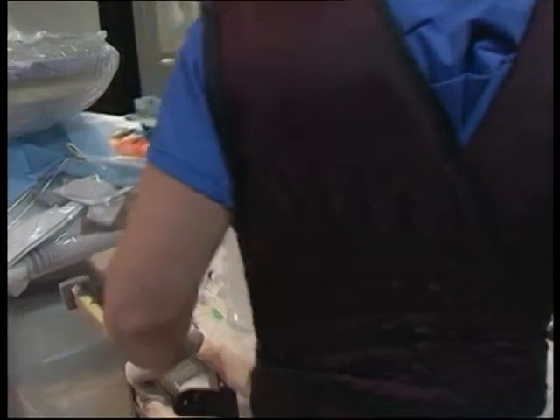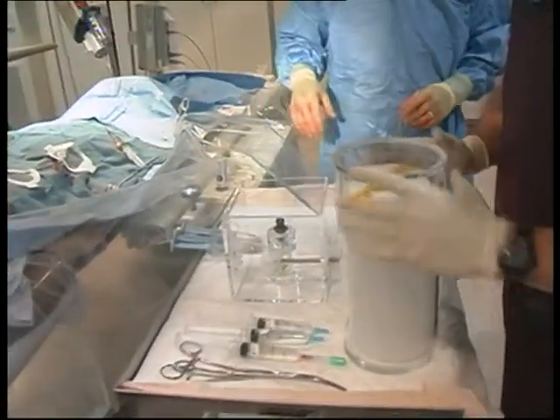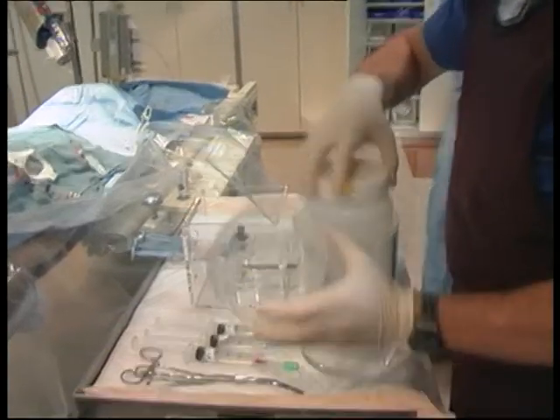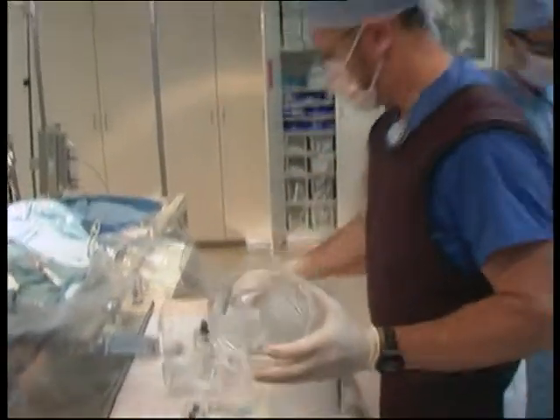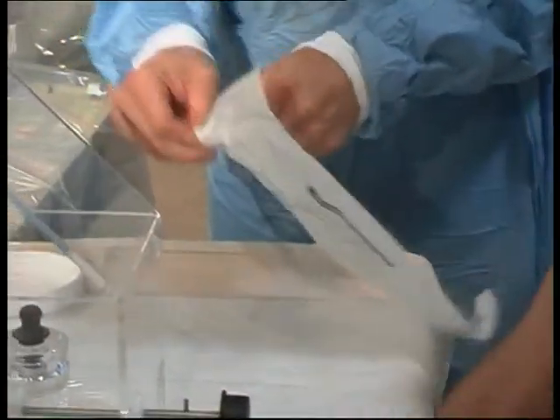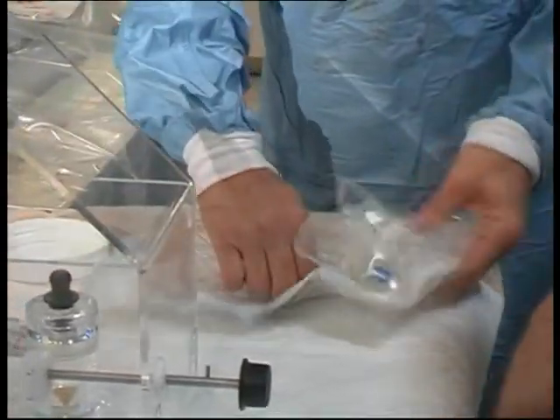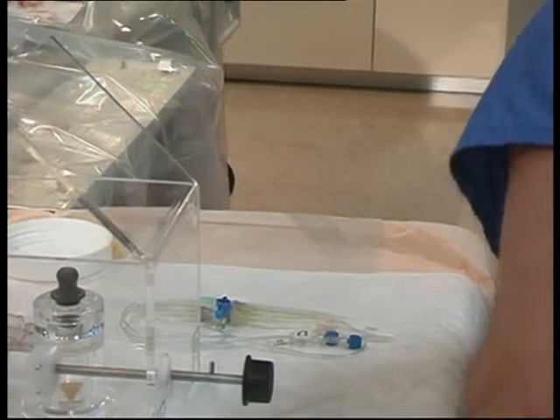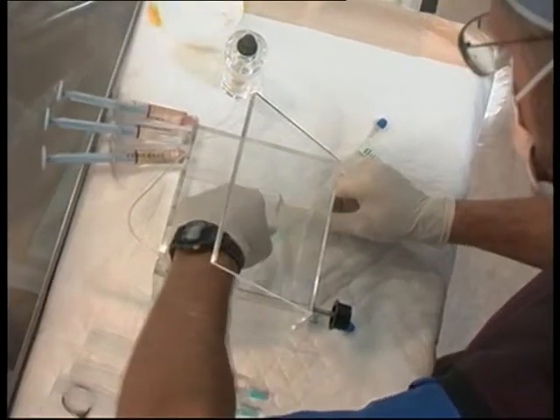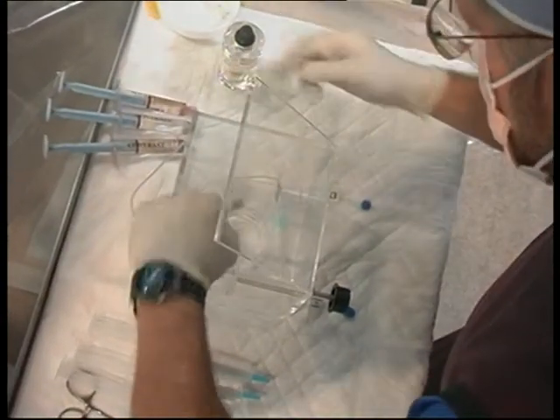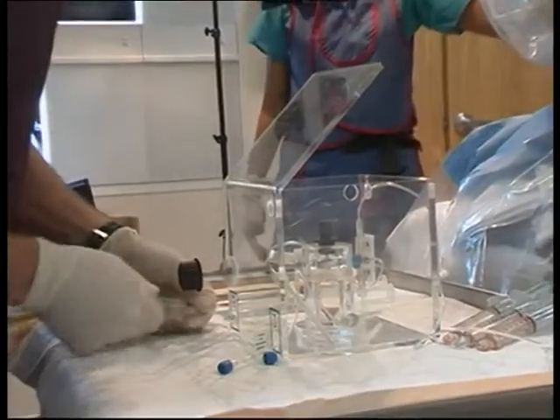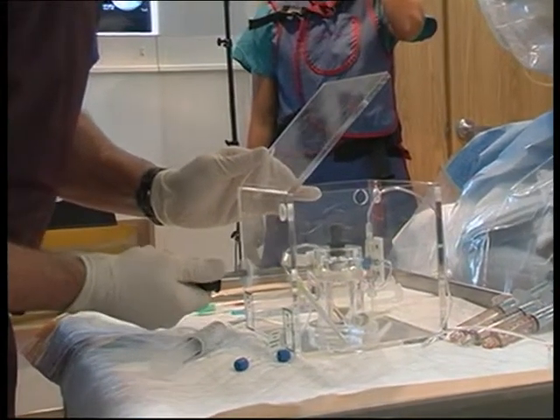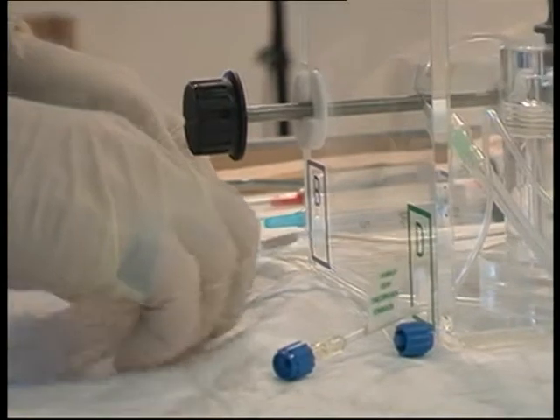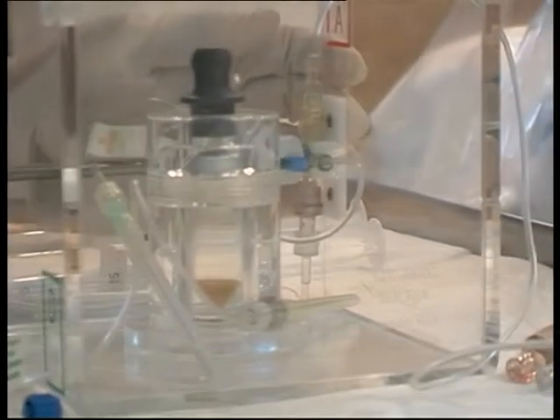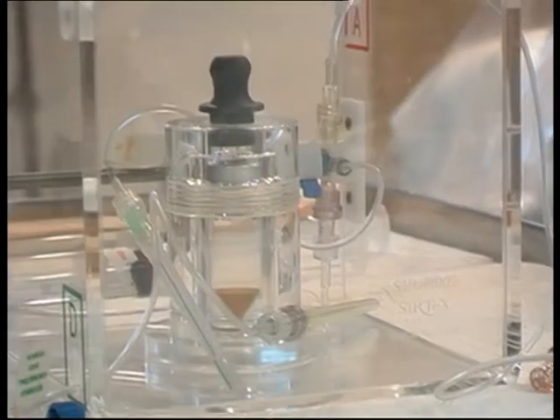Before preparing the delivery box for setup, place it on the right side of the patient. The delivery box should be positioned at the same or higher level than the patient. Open the delivery set and place the lines in the corresponding slots in the delivery box. So we're just priming the lines with water. Make sure all lines are primed with sterile water.